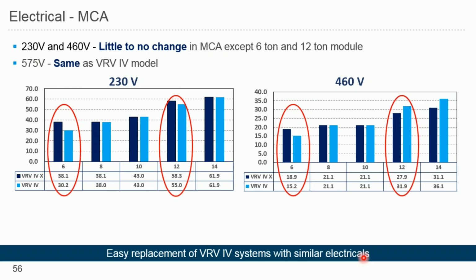MCAs and MOPs, things to keep in mind for the 230 and 460-volt models. For the 6-ton model, the chassis is getting bigger. Now for all tonnages, 6, 8, 10, 12, and 14, we'll be using the same chassis dimensions. So you're seeing some increases in MCAs for the 6-ton model, and the 12-ton model is also something you have to keep in mind, that you will be seeing a small amount of increase in MCAs.